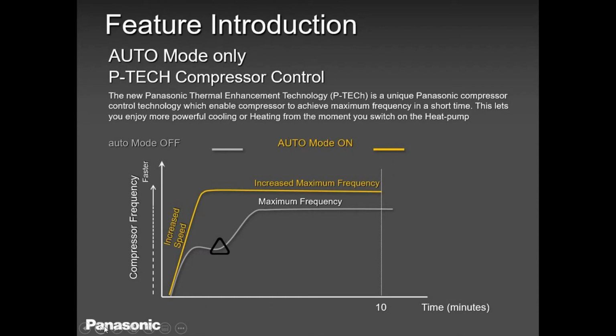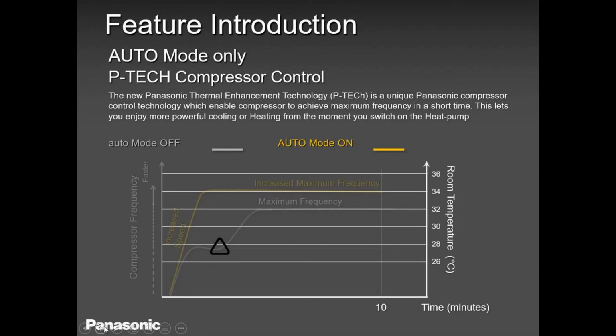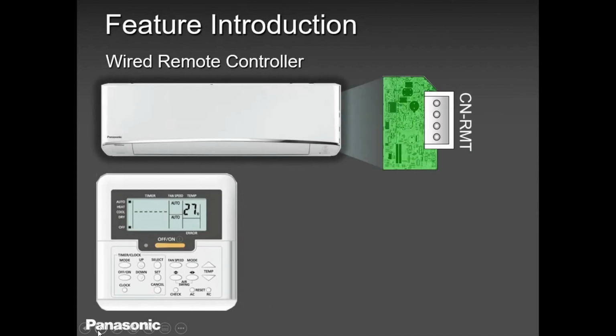Okay. So in those 10 minutes, you can check many things, like running amps, gas pressure, and all that kind of thing. Many guys will call me and tell me, Paul, my indoor fan is not ramping up. I think the problem is the indoor fan. No, it could be the sensor, or it could be the refrigerant.